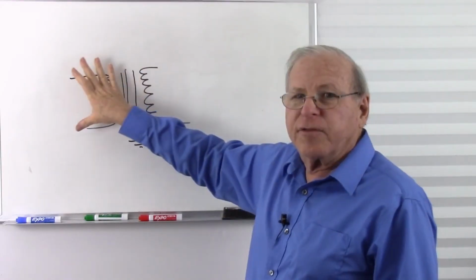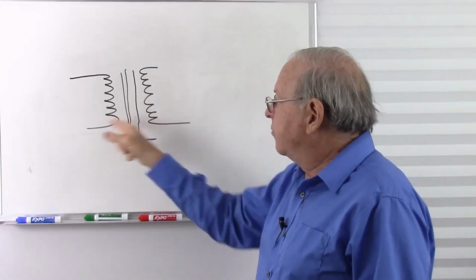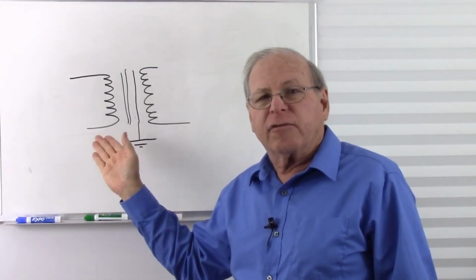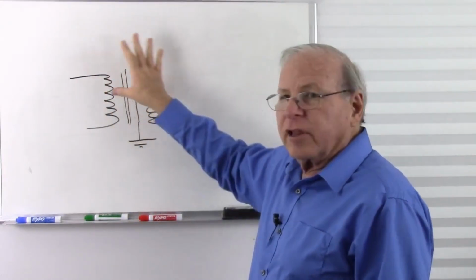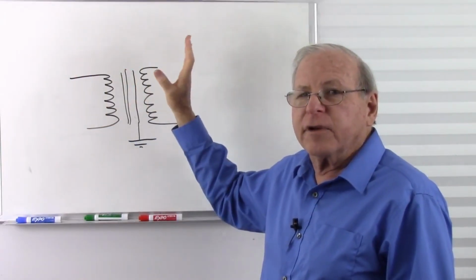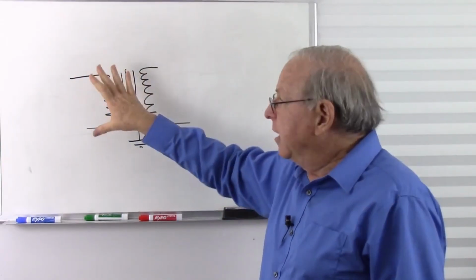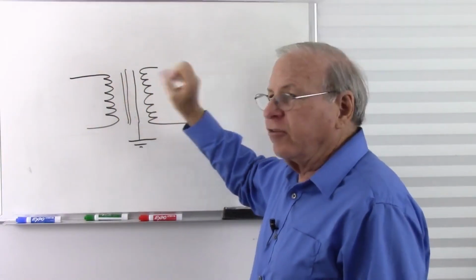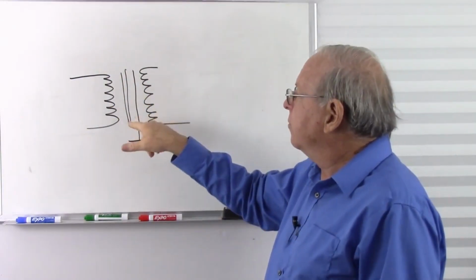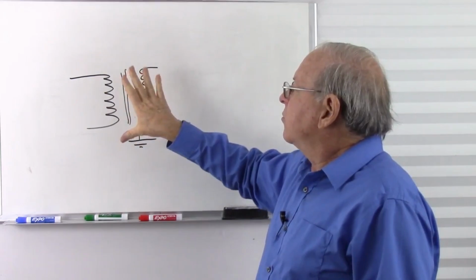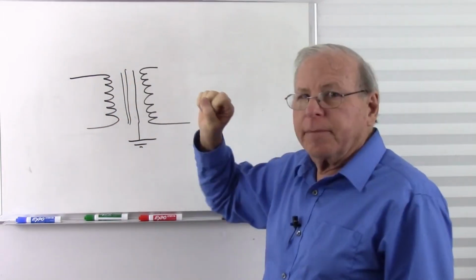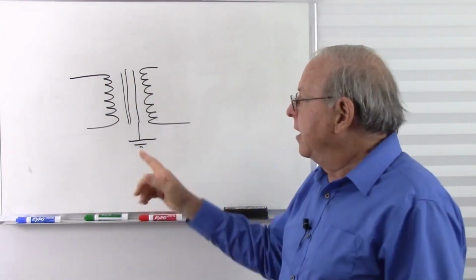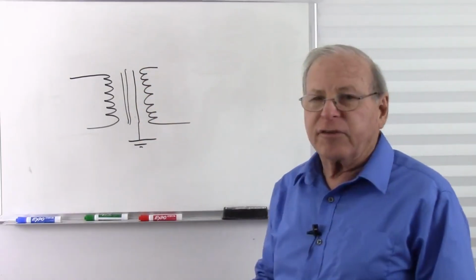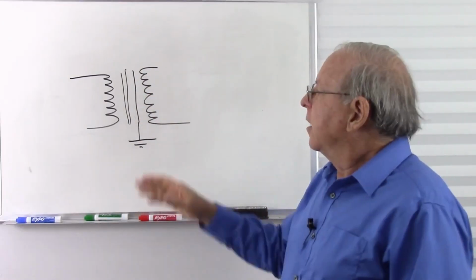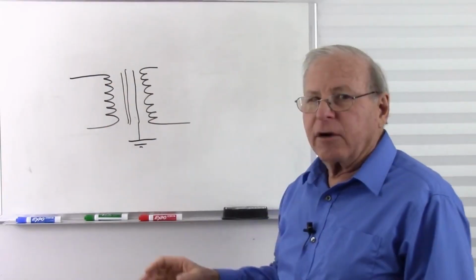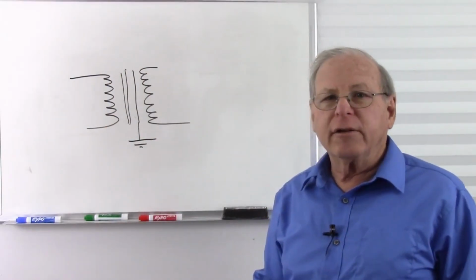A transformer by its very nature isolates us galvanically, so there's no electrical connection from one side to the other. We have good insulation to reduce any kind of current leakage that might get through lesser insulation, so we don't have any microcurrents flowing through. We separate the coils so we have the minimum amount of capacitive coupling, and we put a Faraday cage around the secondary, most likely the secondary, to prevent any electromagnetic radiation from getting from one side to the other.